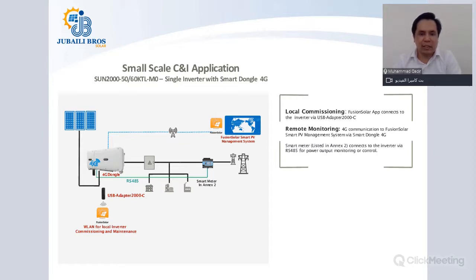A small scale C&I application. Local commissioning: FusionSolar app connects to the inverter via USB adapter 2000C. As I said initially, the 36 kilowatt and above size low voltage inverter comes with the free USB adapter, which can communicate via Wi-Fi to the FusionSolar app. So you can connect the FusionSolar app to this device. Alternatively, you can also connect the Sun 2000 app to this device for local commissioning. For the remote monitoring, in this scenario, you can have the option of using 4G dongle, and you can do the remote monitoring through that dongle device.